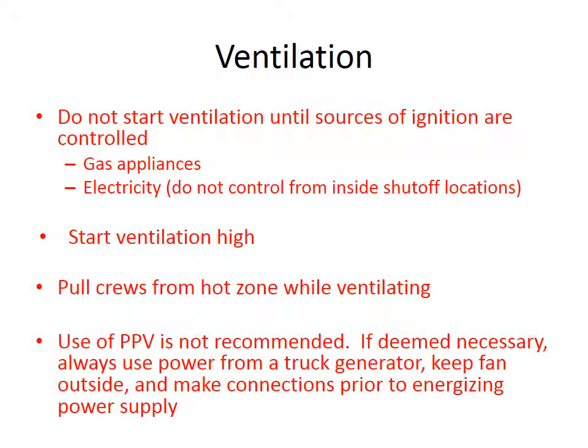Okay, do not start ventilation until ignition sources are controlled. We talked about that. Do not control the electric utilities from inside shut-off locations, so we don't want to be going to the breaker panel to shut them off. We want to ideally get them disconnected from the exterior by the power company. If we're ready to do ventilation, we want to start up high. And again, that all goes back to the combustible gas rising.